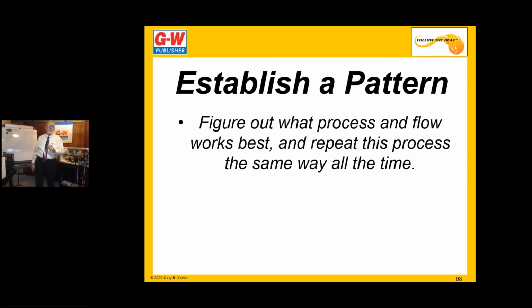It took me about 10 minutes to diagnose because of my pattern, because of starting at the tower. Without shutting it down, because I know if I shut the tower down, it's going to shut the airport down, I managed to get that obstruction, that plastic trash bag, out of the tower. I fished it out of there with a piece of PVC pipe. It was like I was on a fishing expedition. But I got it out of there, and it went back to normal operation. I put on a dry shirt because I got soaked doing it. I always carried dry clothes in my truck.